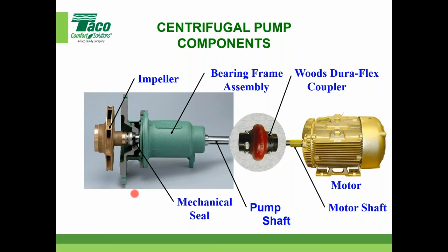If you've ever been to a job site, and I'm sure many of you, if not all of you, have been, there's a little dust and dirt and grime, and the pipe could sit outside, the pipe is moved and there's welding grit inside of it or whatever. And when these pumps are used as the startup pump instead of having some other way to start up the system, that seal isn't going to last. So whatever pump is used for that, that seal has a good chance of leaking before the punch list and before you're off the job site. So just a quick recommendation there.